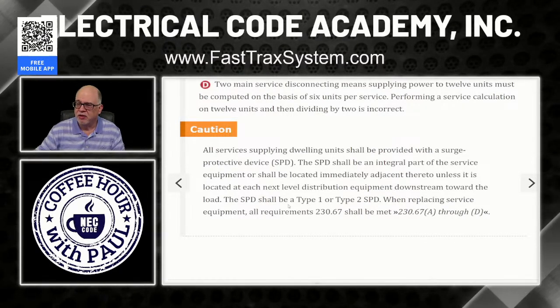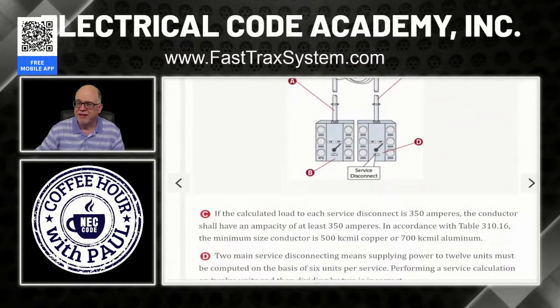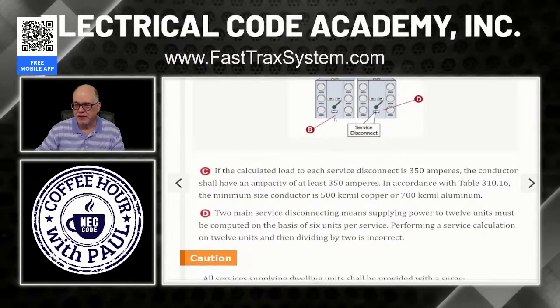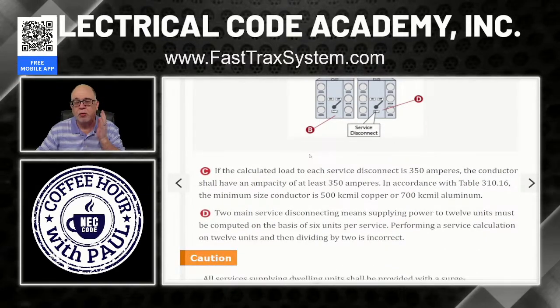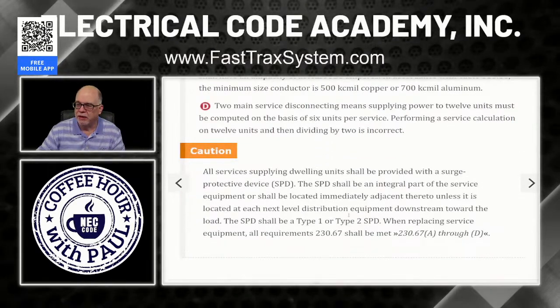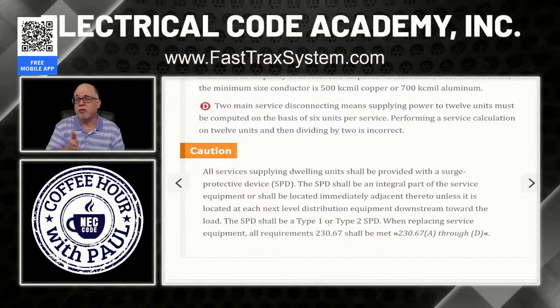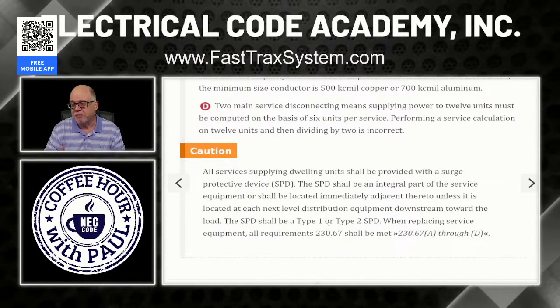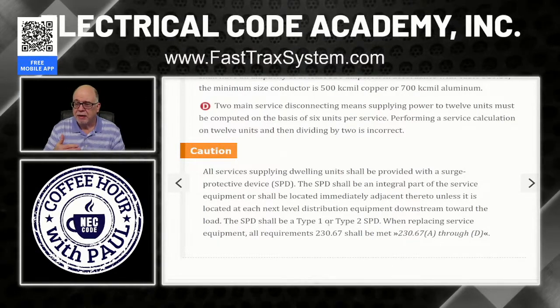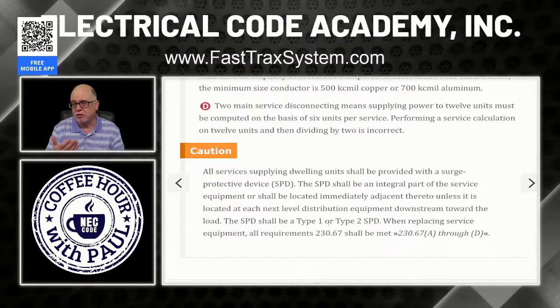So in this case, you can put it at the service or you can put it at the next downstream distribution, which would be at each one of these feeder panels if you wanted to do it that way. And it'd be type 1 or type 2. Now, type 1 typically is on the supply side of the service disconnect, and type 2 is typically on the load side. But check with your manufacturer, because I believe manufacturers make some type 1s that can go on the supply side or the load side.